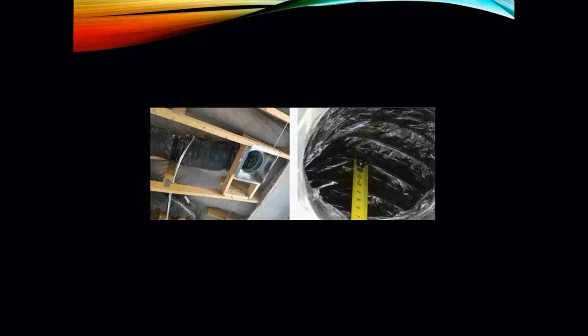So if we look at this particular image, we have a 10-inch round piece of flexible duct that is getting stretched out, and the register is in a tight corner. Okay, if we look at this tape measure, just because of the area of this register, that 10-inch flexible duct has now been crushed and crimped down to almost looks like about 6 inches in diameter. By doing so, we are cutting down greatly on the airflow and the velocity that is needed for that particular space. So once this home is actually finished and that air conditioning and heat gets turned on, you're going to have an issue with heating and cooling that space because the flexible duct is now crimped down.